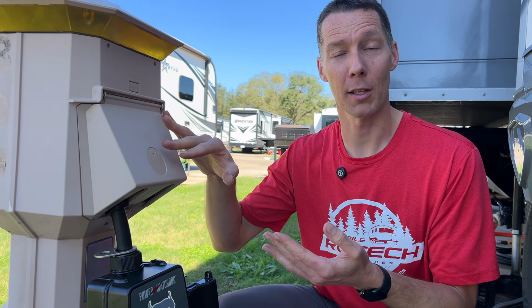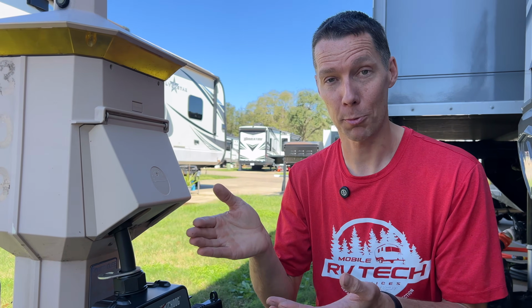If you have a surge protector that is not smart, those have some indicator lights on it, so when you plug in you can see what's going on inside of the power pedestal - the wiring should be correct. They're not monitoring voltage or amps, just looking at the wiring itself, and they do not shut the power off if there's an issue. Compared to the Watchdog type, the smart ones have an EPO, emergency power off - they'll shut the power off if your voltage goes too low or too high, the amperage is out of range, or the wiring starts melting. It shuts things down before things break inside the RV.